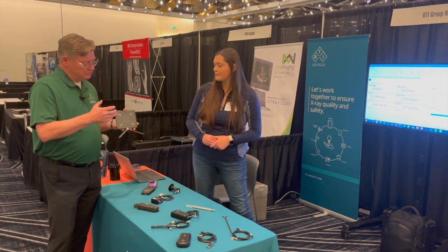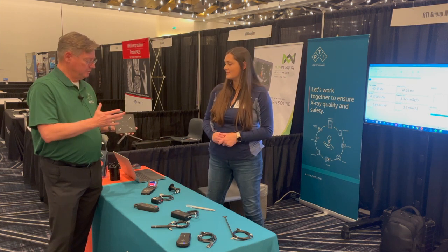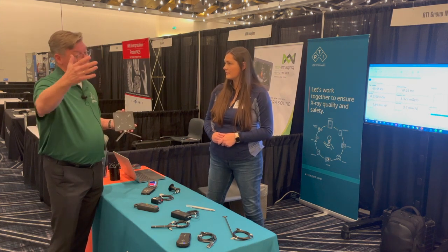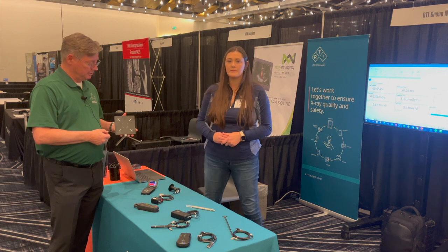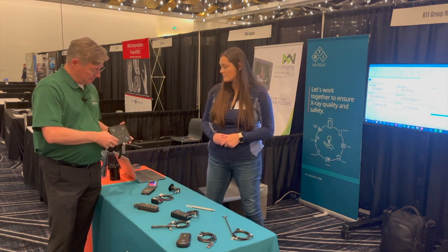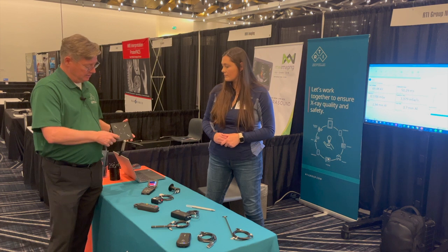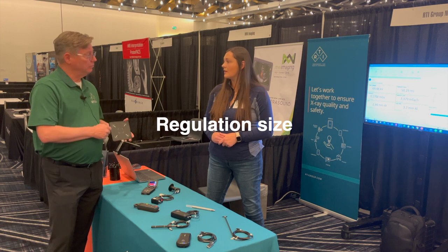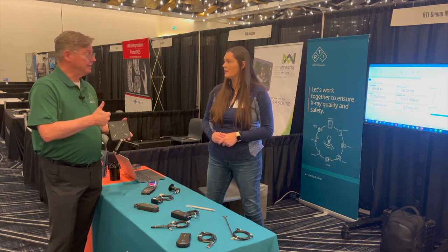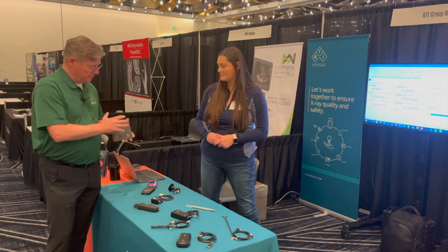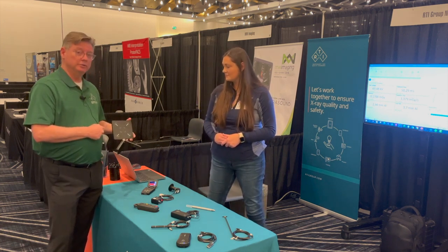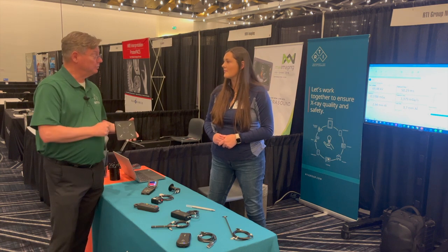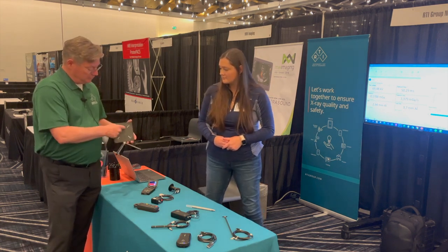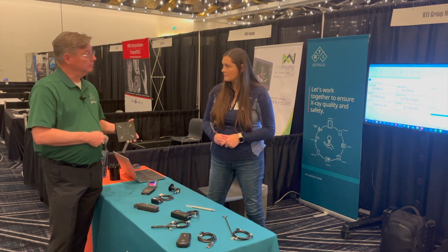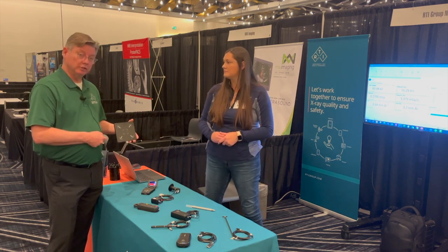Okay. So it makes it suitable for leakage and scatter measurements from mammo all the way up through to CT and even some higher measurements there. Okay. When it comes to scatter. The interesting thing here is that, as you can see, we've got it marked, the active area here is regulation size. It's 100 square centimeters. And that's the size called for in regulation by the IEC as well as FDA. Okay. So it fits that, and you can make those leakage and scatter measurements with just one exposure. Absolutely. So not only the leakage, but also the barrier testing, where you need a 10 square centimeter size area to cover.